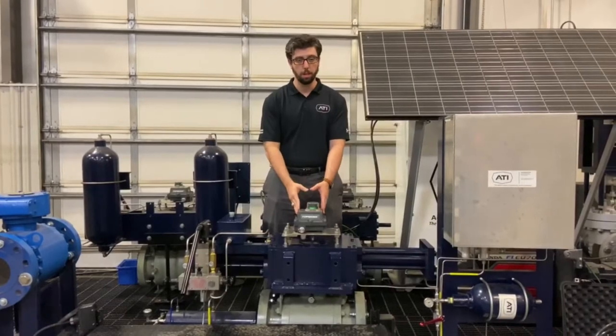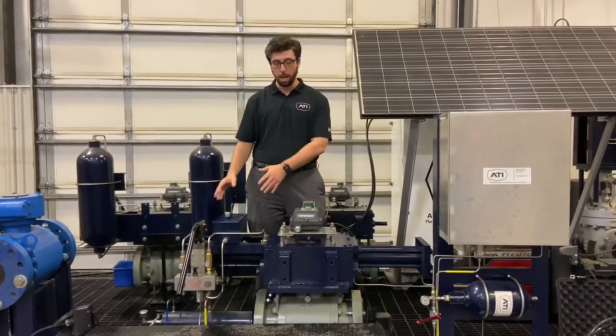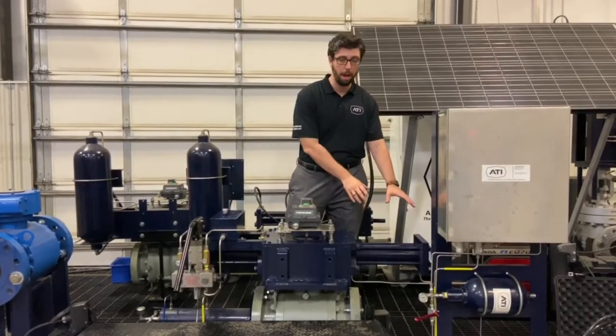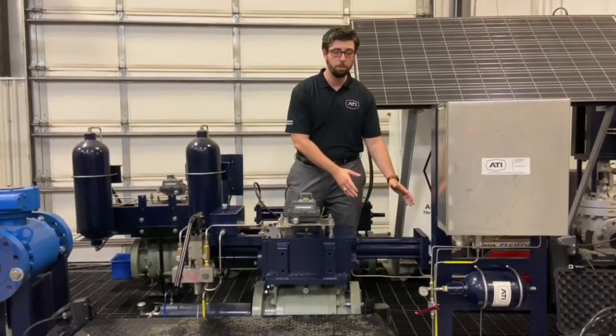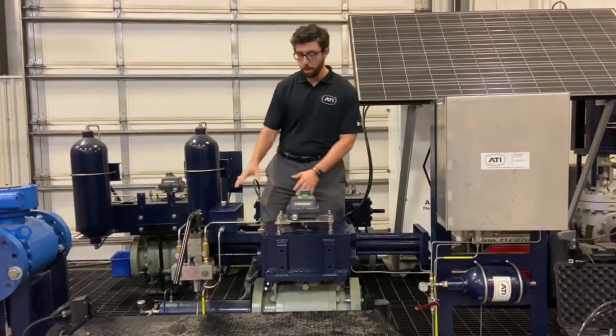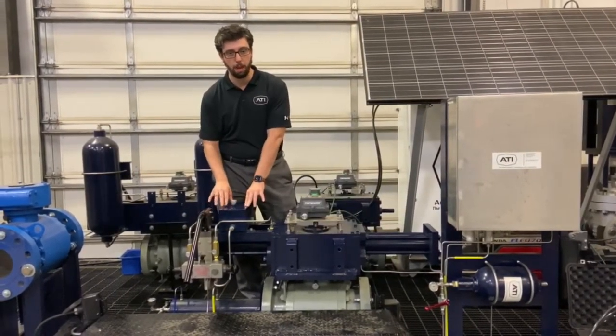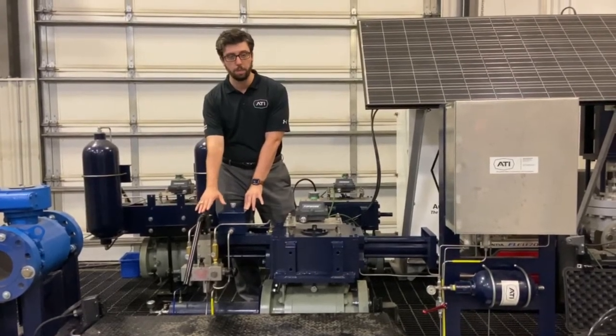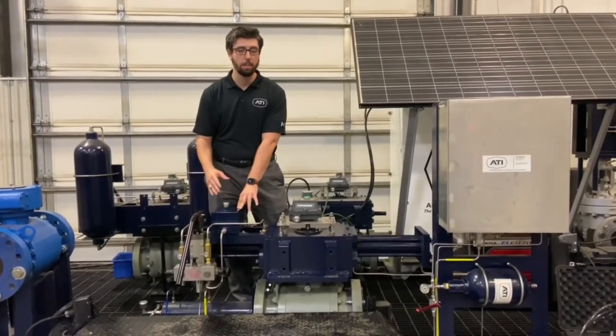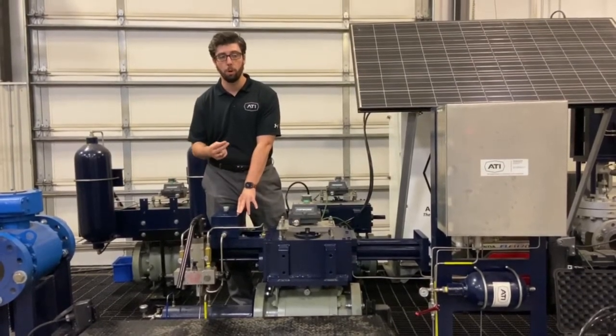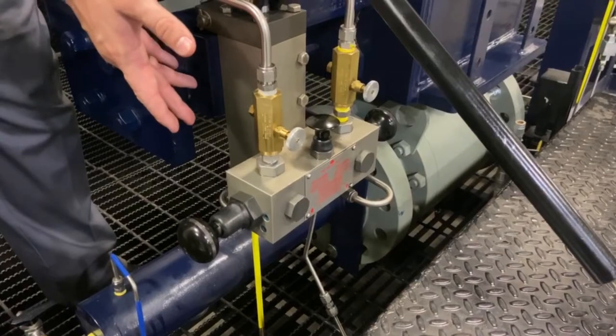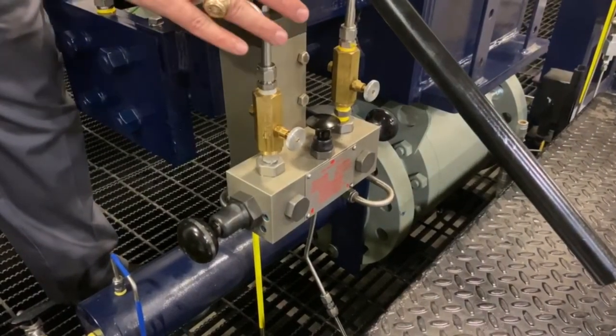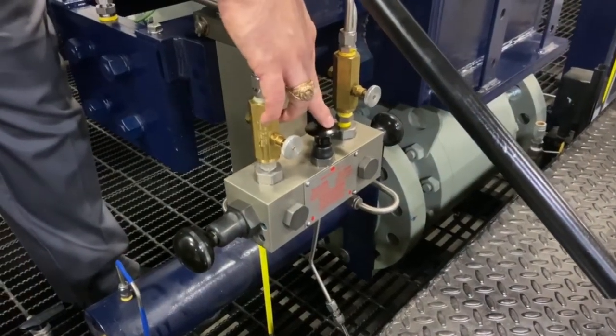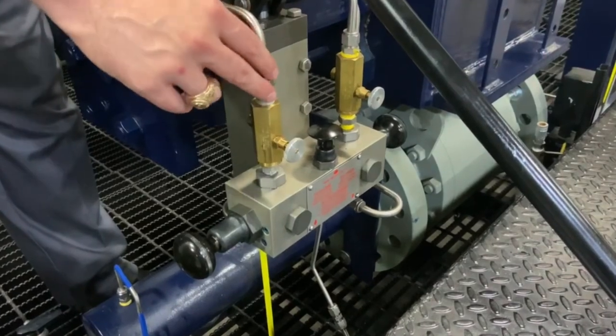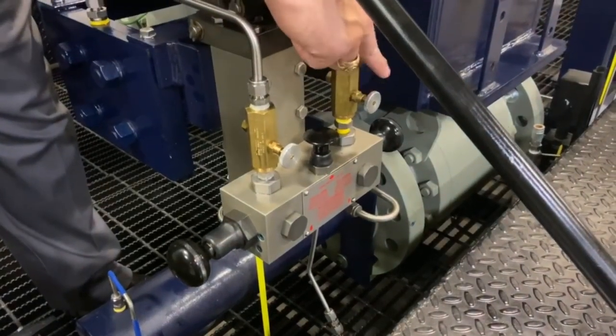In addition to the position indication, our quarter turn direct gas actuator has two different cylinders. This cylinder is for the power gas coming out of the pipeline, which allows the actuator to stroke back and forth. This contains hydraulic oil for our manual automatic reset hand pump override and to act as speed control or dampening effects or cushioning. Here on our hand pump system with automatic reset, we have the ability to close or open the actuator, relieve the hydraulic fluid pressure, and independently control the close and the open speeds if that is so required.